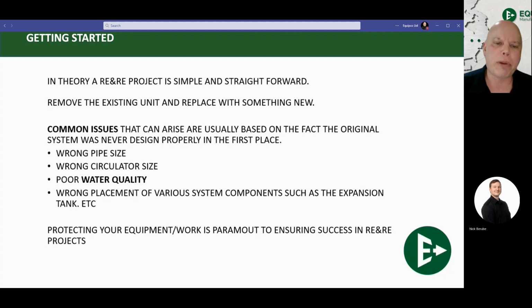Last one on our list is the wrong placement of various system components, such as the expansion tank. All I want to say about this one, because this is going to be a bit more of an in-depth conversation, is that a lot of the times we have pieces in a system that are required, but they're put in the wrong place, which causes us problems usually with flow or with dirt and debris inside of a system. So it all goes back to the three pieces that I just mentioned. If we have pieces in the system in the wrong place, that can lead to poor water quality. If we have pieces inside the system, again, that are in the wrong place, such as your expansion tank going where it shouldn't, that'll affect your circulator sizing, or it can cause an undersized circulator to perform very, very poorly, and it'll make you need to oversize your circulator, which can be very, very expensive.